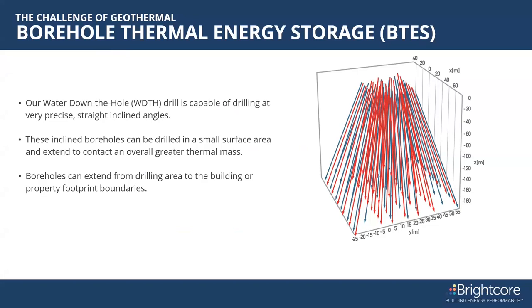Now, in geothermal, we love passive housing. The efficiency, the envelope is so efficient that it really reduces the number of holes, and therefore cost, but also the electrical load. Air source heat pumps, we're not against them in any way. Ground source heat pumps have their advantages. For example, right now, I'm staring at a reading of about 6 degrees Celsius. Air source heat pumps pulling heat out of 6 degree centigrade air to heat up a room are not as efficient as you would have down below within a ground source heat pump, removing heat that is constantly roughly between 50 to 60 degrees Fahrenheit, or about 12 to 17 Celsius.